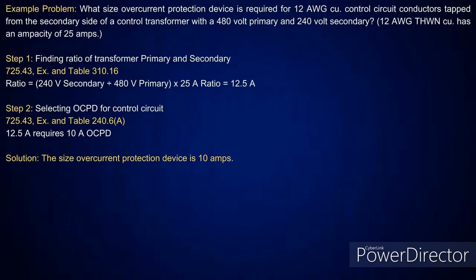All right, then we're going to do another one here. And this is where we're going to size the overcurrent protection device. What size is required where I have number 12 control circuit conductors that are tapped from the secondary side of a control transformer, and the primary is 480 volt and the secondary is 240 volt. Okay.